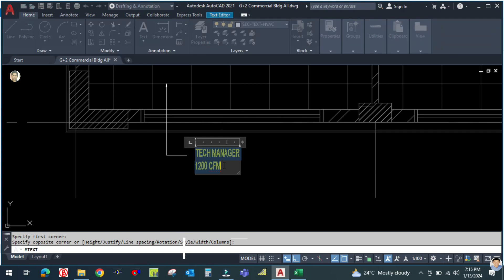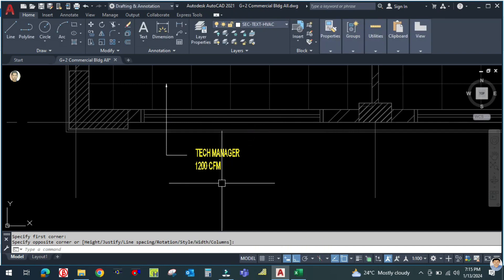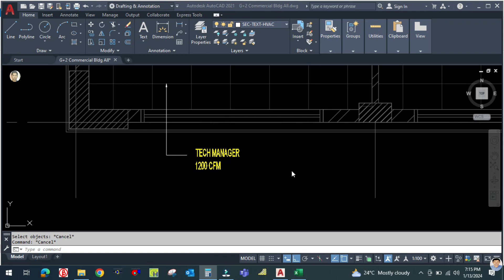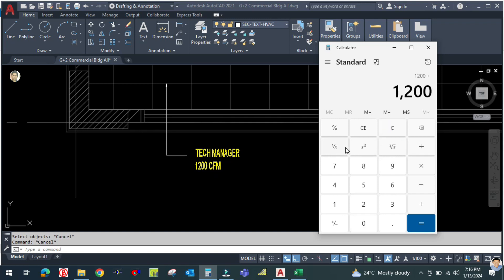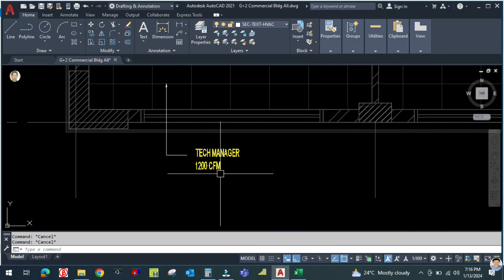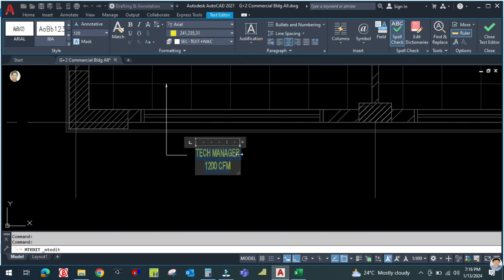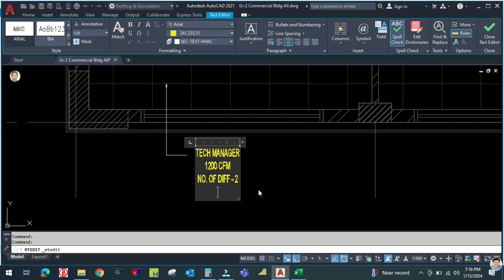We have to pass 400 to 500 CFM through each diffuser. The number of diffusers equals 1200 divided by 500, which is 2.4. Or you can pass 600 CFM per diffuser. As per the area, the number of diffusers is equal to 2.